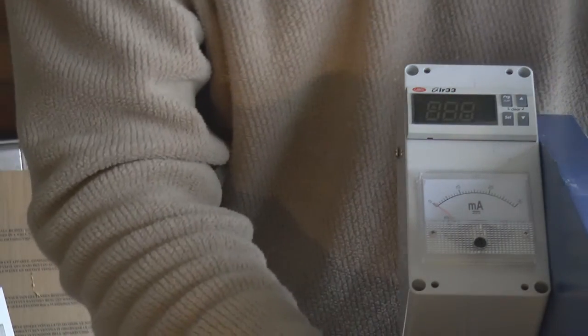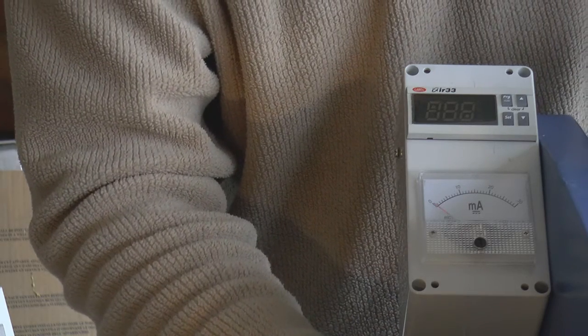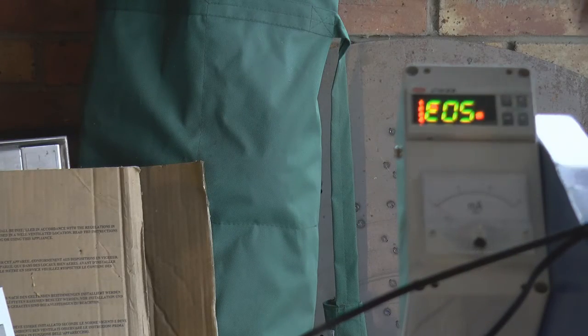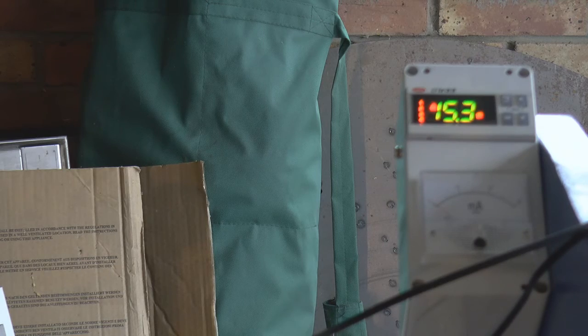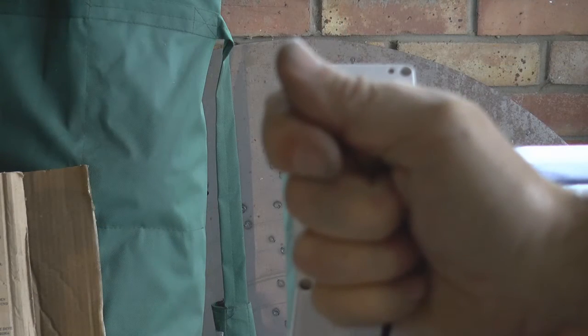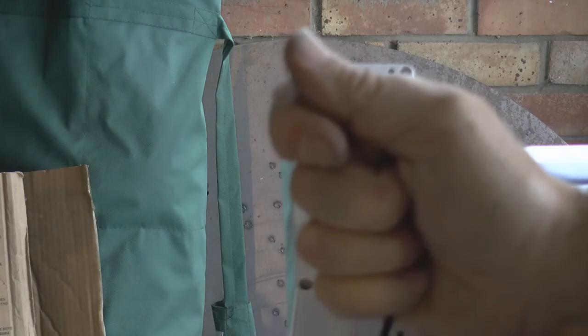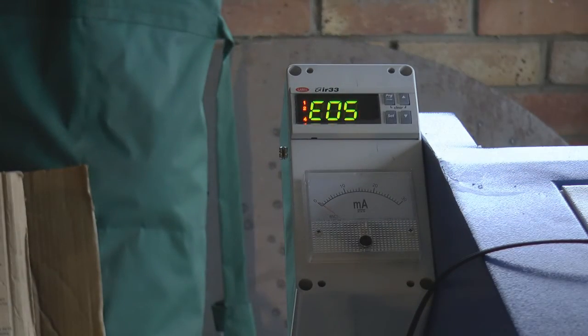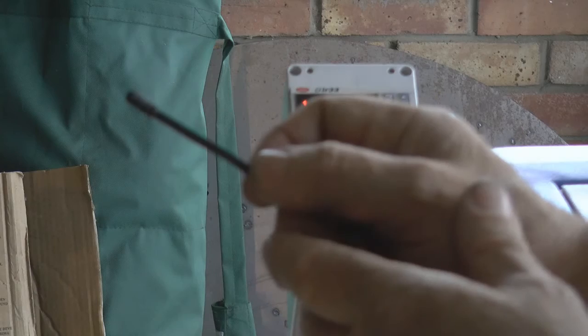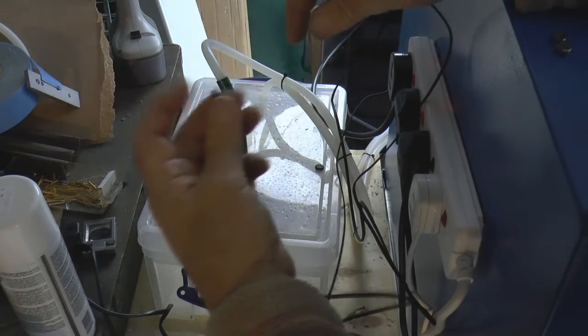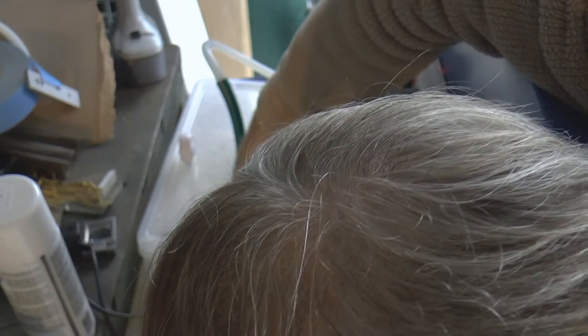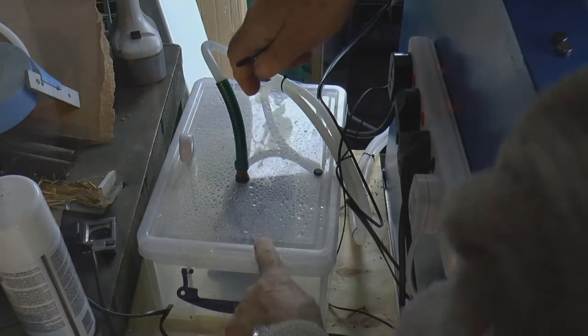Here I've got a special connector that goes into the back of that instrument. They are connected into its little terminal block. We've got another little terminal block which plugs in the back for the mains power. We'll turn the power on. There we go - basically 15.3 is the temperature of one of these probes at the moment, which is probe number one. You'll see it starting to go up - 19, 20. So this is the probe that's being displayed. We need this one on the return line from the tube and this other one we'll drop into this end.